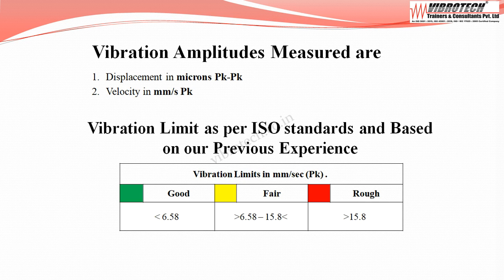As per ISO standard and based on previous experience, the vibration limits are as follows: when velocity falls below 6.58 mm/s peak, it is considered good; between 6.58 and 15.8 mm/s peak is considered fair; and above 15.8 mm/s peak is considered rough.